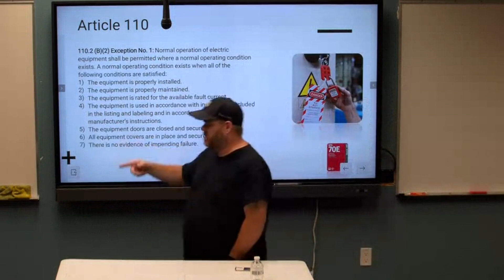And I'll show you some examples of exposure. That's one of them, actually. Now, the exception to what we just talked about, okay, the 70E allows normal operation of electrical equipment where a normal operating condition exists. Now, I think this is where a lot of electricians go wrong. They approach existing equipment, panels, disconnects, whatever, and they start opening them up and digging into them. What we're required to do is first take a few steps back, take a few deep breaths, and look at it and see if it appears to have been installed correctly to the 70E, right?